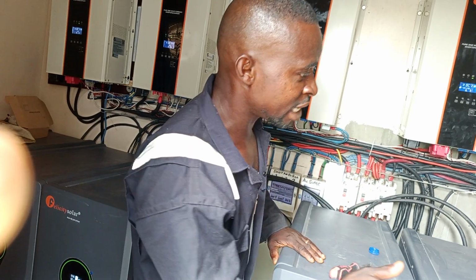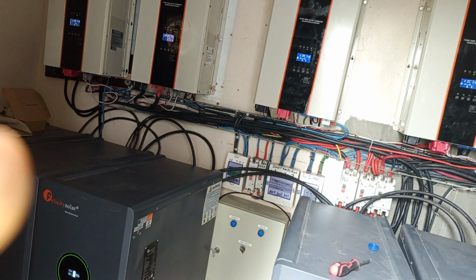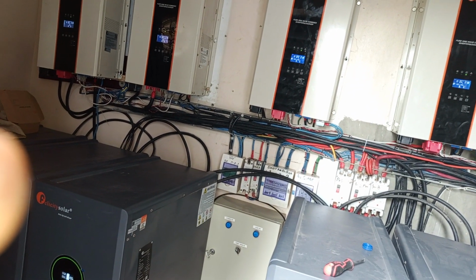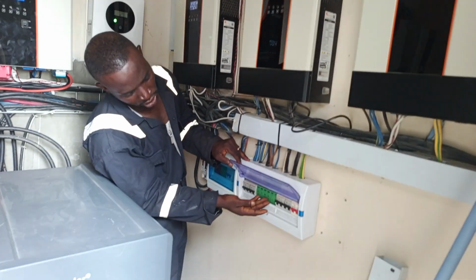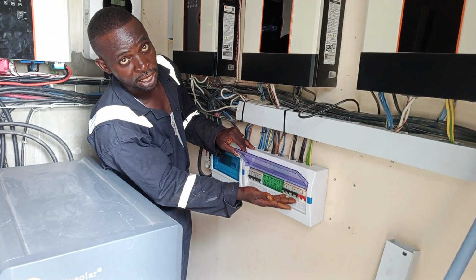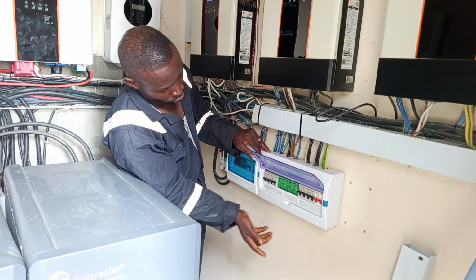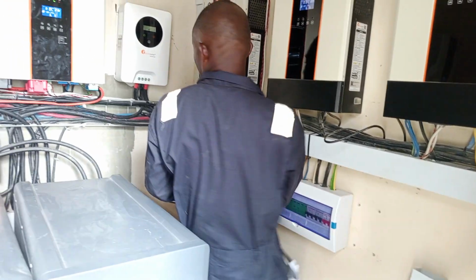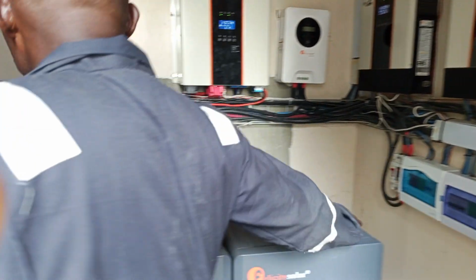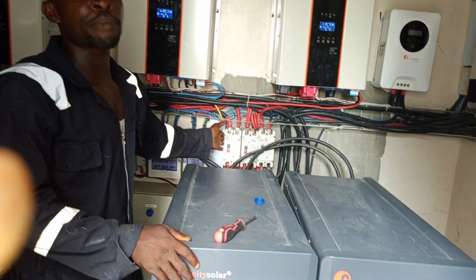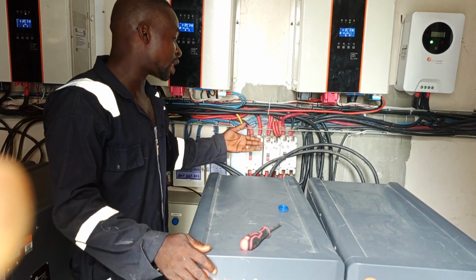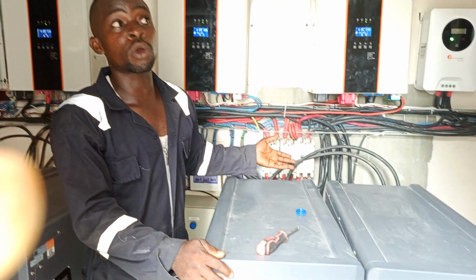So guys, as I said, these are the control boxes. This is our protection system, our DC breaker and AC breaker. This is our surge protection, just like that. And then this other one, you will have to size the rating of your PV, then that determines the type of breaker that you are going to use.